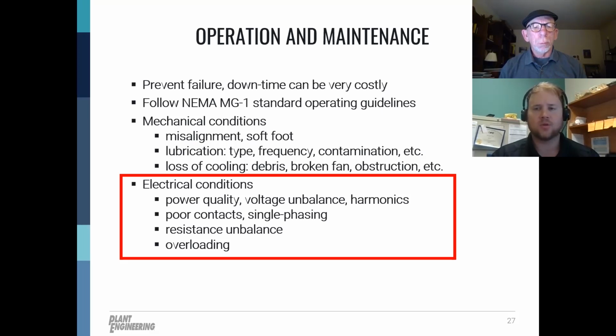Also, just make sure when you are adding grease to the motors, clean those nubs before you hook up to the grease fitting and add the grease. Most motors today, you're going to be using Polyrex EM. Keep some tubes of that around so you don't have to run out and buy some all the time. This is very common across the industry, so it's good to have some tubes of that. It's blue. And then another thing you can do, keep the fans checked for obstruction. Make sure no stray debris gets inside the fan or inside the fan shroud.